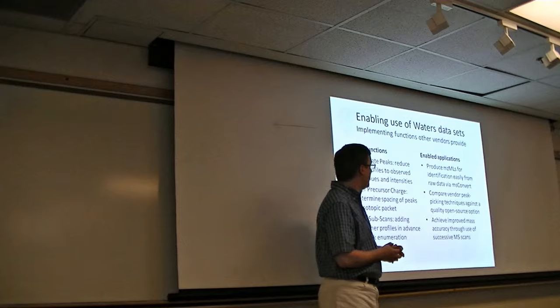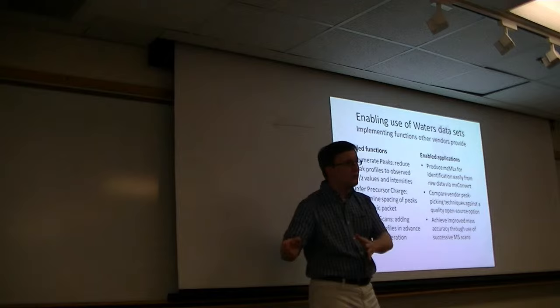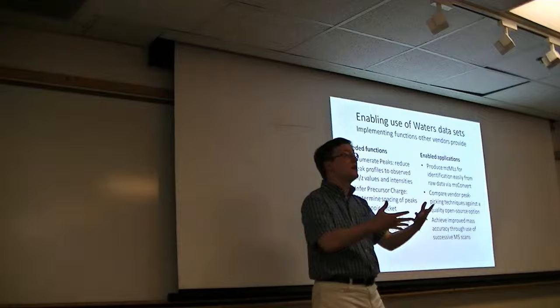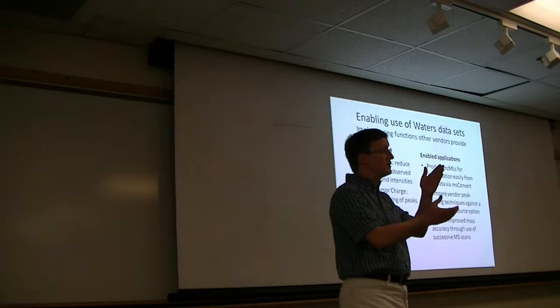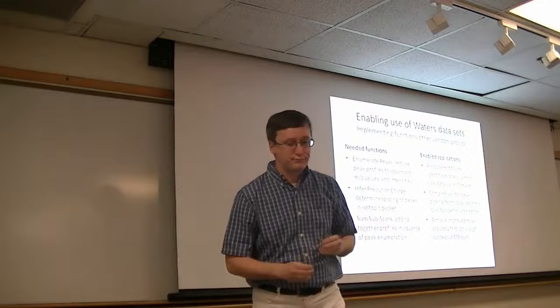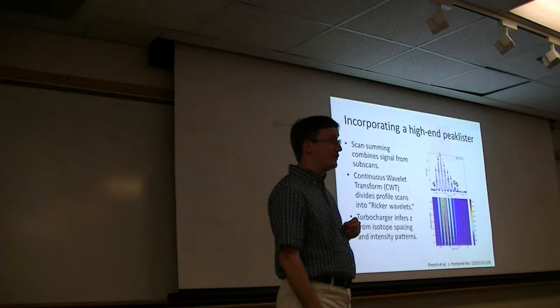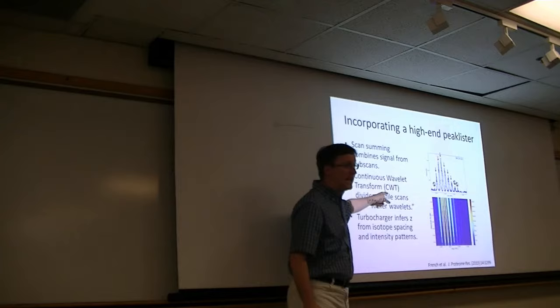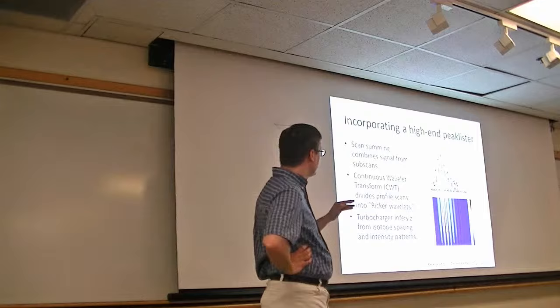We needed to have a high-quality open source implementation for how to do peak picking to compare against what other vendors are doing. So, whether we're applying this in Waters instruments or not, we wanted to be able to generate a peak list that reflected our method for doing it. And, of course, wouldn't it be nice if we could even improve upon the mass accuracy that's delivered by these vendor libraries? If we're able to make use of information, you know, several seconds before and several seconds after to really refine these mass-to-charge values, that would be very powerful. This is a trick that's been done in MaxQuant, for example. So, what we've done is to create a really high-end peak picker that's applicable in Waters instruments. And for this, we've used a trick called continuous wavelet transform, which is why we call our method CAN'T WAIT, as you can see. It also sort of fits in there. So, we needed the ability then to map what are called Ricker wavelets to the data that we've observed. A Ricker wavelet is more frequently called a Mexican hat wavelet. So, it occurs sort of like that.